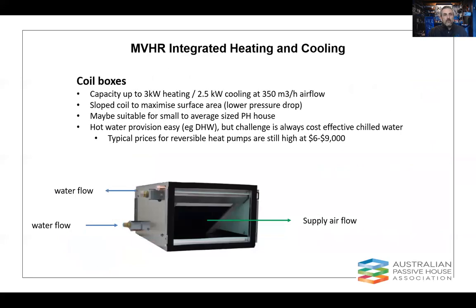The other component we've got there for integrated heating and cooling, and this is not particularly new, but it's just a slightly different concept on an old idea, is coil boxes. And so these are post heating or cooling. Post meaning you've had your outside air, it's come down through your MVHR unit, you've recovered as much heat or cool as you can, and you need to do a little bit more cooling or heating.